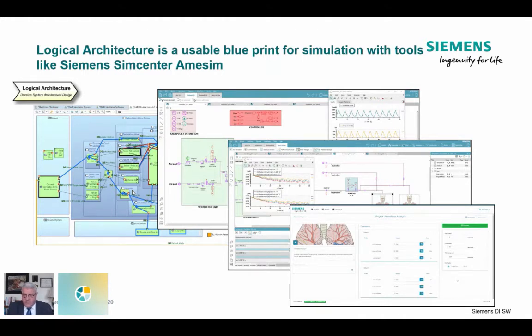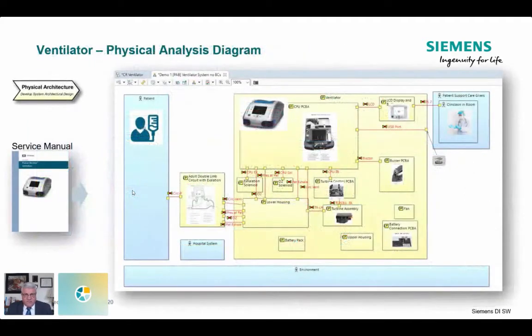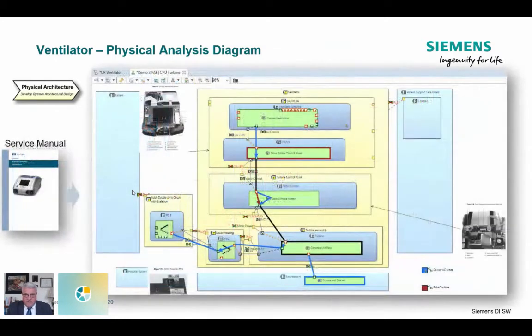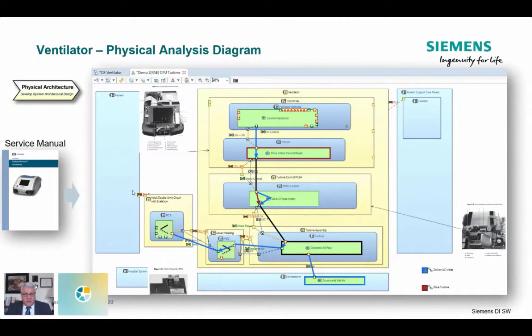Then I started moving more into the physical phase. In the physical phase, we took the service manual as the source and I was able to take that service manual to start detailing what were the various parts of the system. I incorporated graphics and pictures to help people see what the various parts were and started denoting the physical interfaces between parts. I then went one step further and started mapping the functionality of these physical systems — the software in the ventilator software, the CPU I/O board with its physical details of drive and motor control, the motor control board, and the turbine generating airflow through the system.